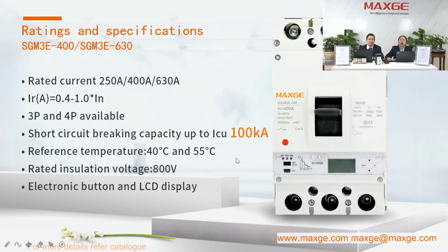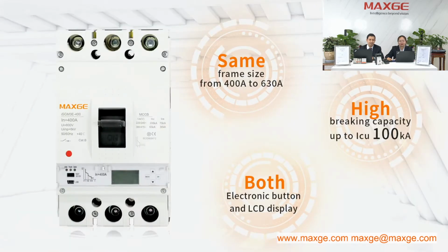Also, all our MCCBs can be operated at temperatures of 40 degrees and 55 degrees. As you know, in Africa and the Middle East, the operating temperature is very high. Under such operating temperatures, our MCCB performance will not be affected. Here, same, for 400 and 630, we have the same frames, same size, as on the competitor side. And here we have both the button type and the LCD display, with high breaking capacity.